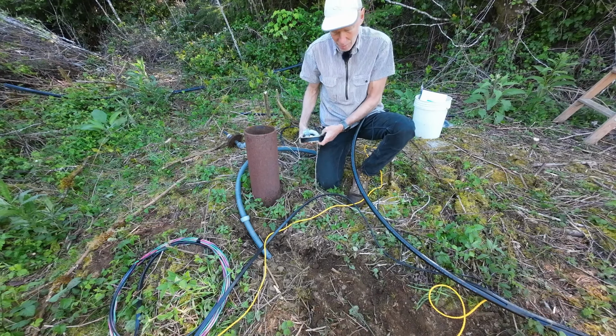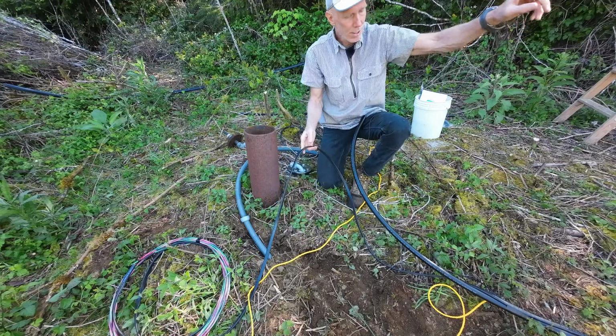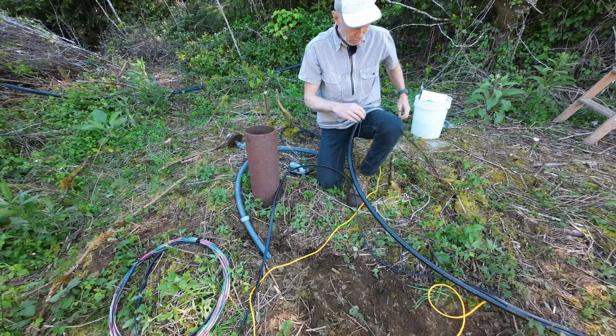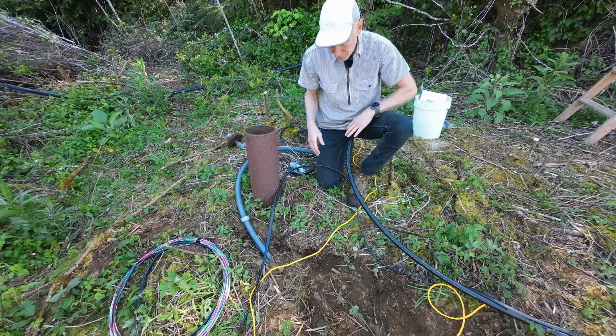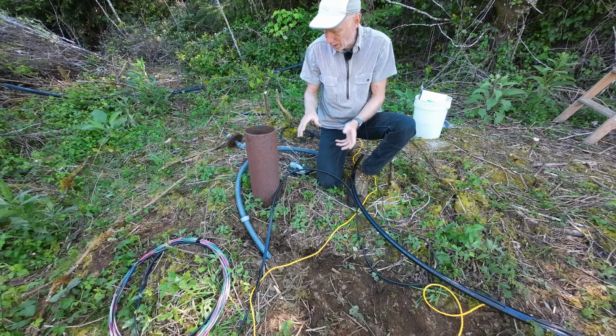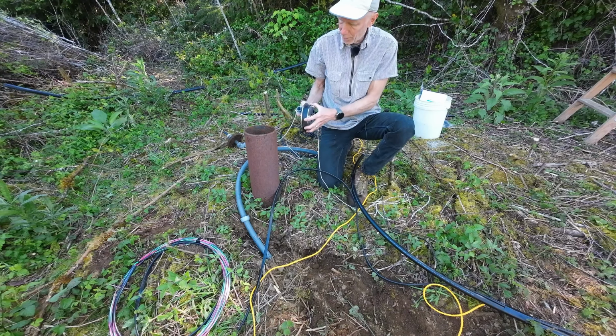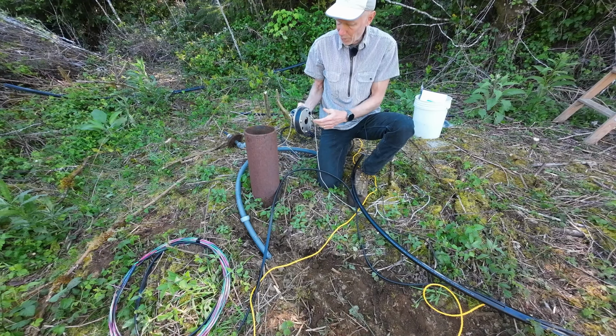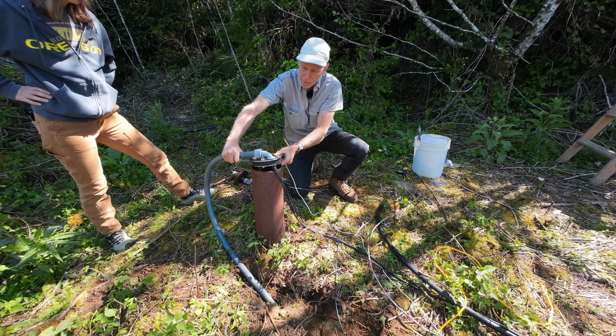And I'm glad I spliced it, because the splice for the pump wire is going to end up somewhere inside the conduit. Looks like they gave me quite a bit of sensor wire, so I'm guessing I won't use that. I can use that somewhere else. But now I need to sort of weave these through and get it all put together. I can basically assemble the low end of this pump head, or pump seal rather. All right, so now we got our wires so that can sit and mount down there.